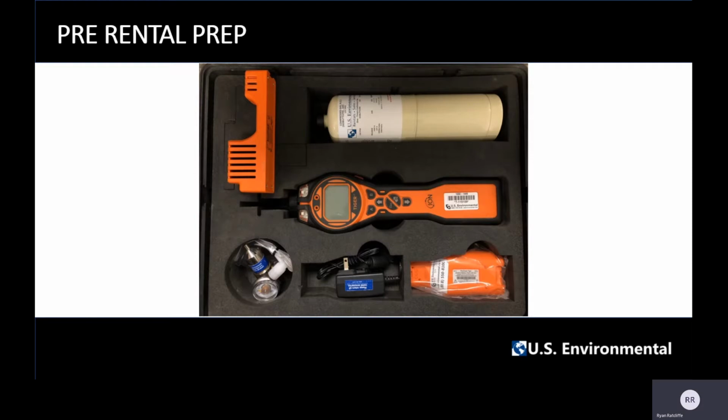Once the calibration is complete and the instrument is cleaned and the case is ready, this is an idea of how it's packed. I'm going to note that the gas is in this case. However, if it's being shipped, you would not ship it in this packing case. It would go in its own box as a hazardous goods shipment.